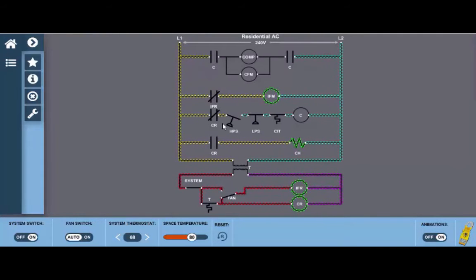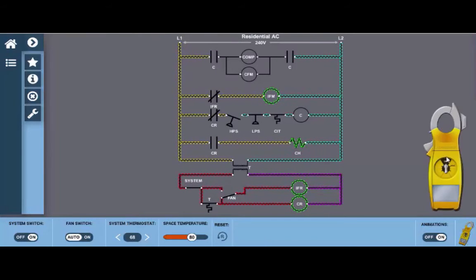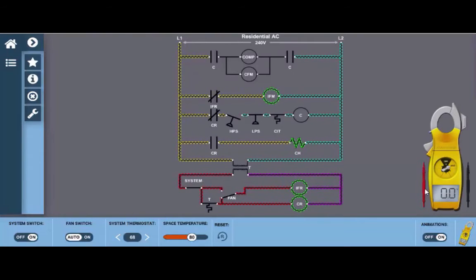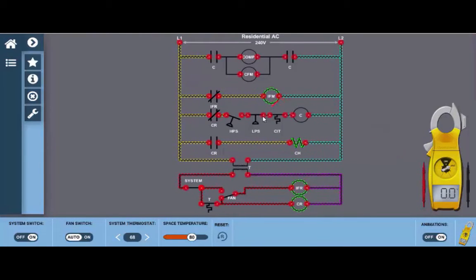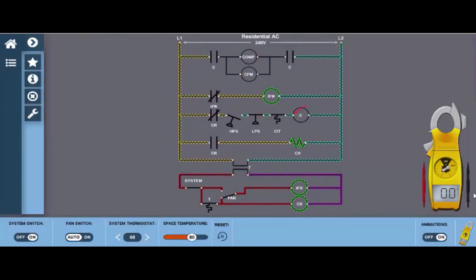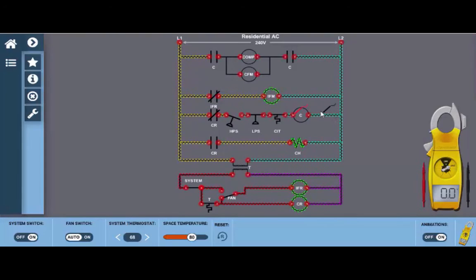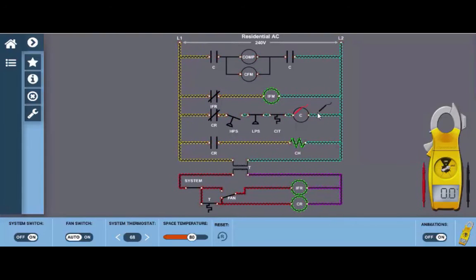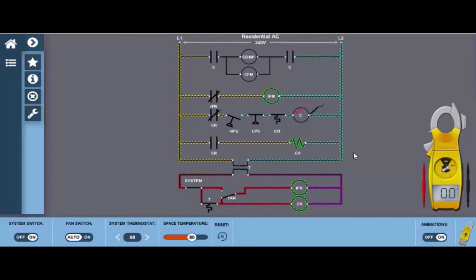But since we selected the high pressure switch we know that that's the fault and you can click on the meter here at the bottom right, turn the selector dial to AC volts and we can simply drop the leads at any of the glowing hot spots on the diagram. In this case here I'm going to start at the contactor coil. That would be probably a logical place if you didn't know what the fault was. When we click here we can see we have no voltage present at the contactor coil which now indicates that we've got a problem with either one of the safety switches or possibly the CR contacts.